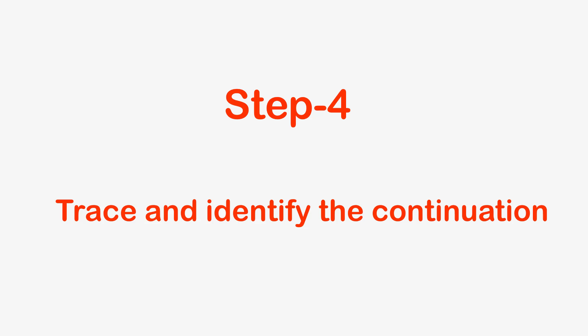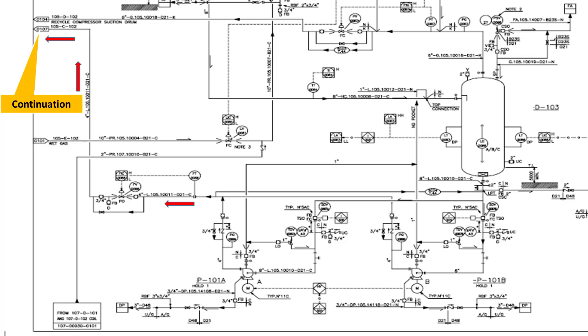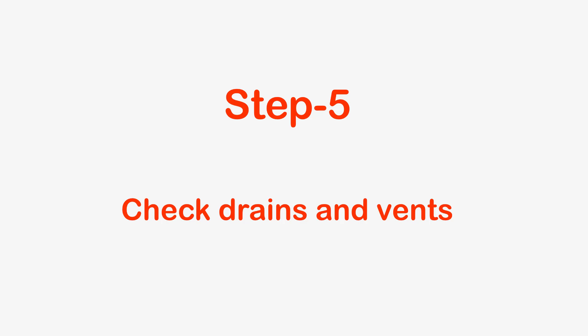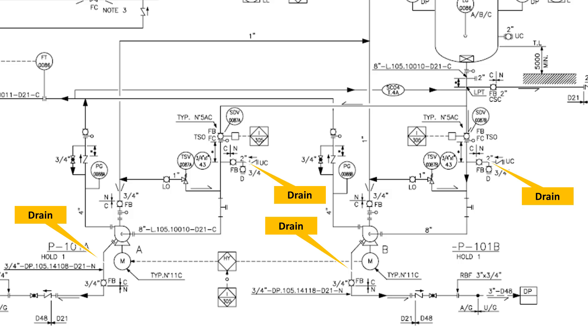Step 4: Trace and Identify Continuation. Trace the line all the way to the end to identify the continuation of the line. If it goes to another P&ID, take out that P&ID and trace the line to find where it goes and is connected. Step 5: Check the drains and vents of all the lines. Now that we have identified the supply and discharge lines, associated lines, and continuation, it's time to identify the vents and drains available in the lines.